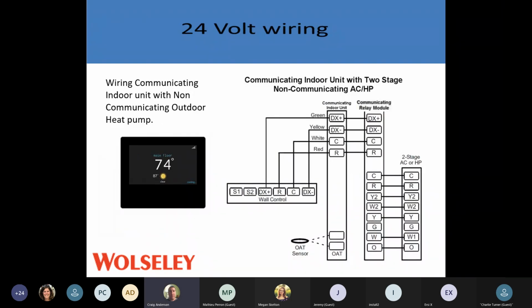So if you're working on a communicating system that has a communicating stat and a communicating indoor unit, and the customer has an existing heat pump or 2-stage air conditioner and they want to keep it, we can hook it up to a communicating system, but we have to add a communicating relay. When we get into a heat pump or a 2-stage AC, we have to add another computer board to a furnace in that state. So if you get a communicating system inside and a non-communicating system outside, chances are there's another communicating relay hooked up to that furnace that you might need to check for voltage signals and stuff.